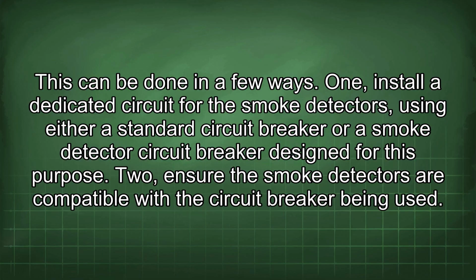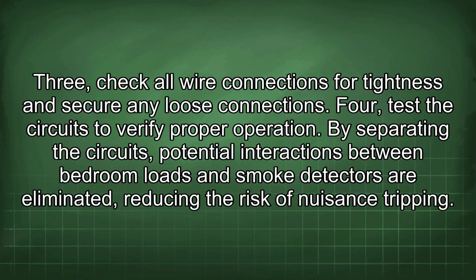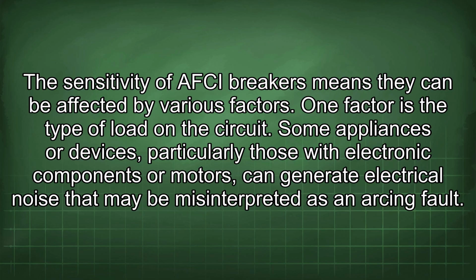2. Ensure the smoke detectors are compatible with the circuit breaker being used. 3. Check all wire connections for tightness and secure any loose connections. 4. Test the circuits to verify proper operation. By separating the circuits, potential interactions between bedroom loads and smoke detectors are eliminated, reducing the risk of nuisance tripping. The sensitivity of AFCI breakers means they can be affected by various factors. One factor is the type of load on the circuit.